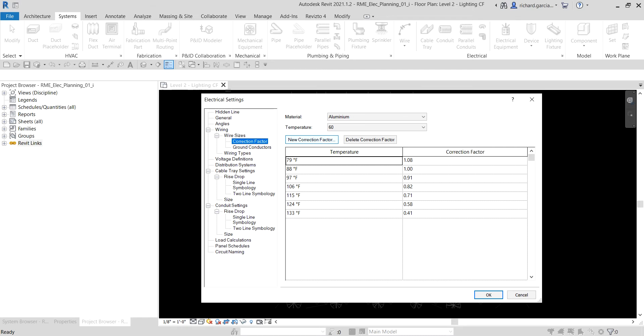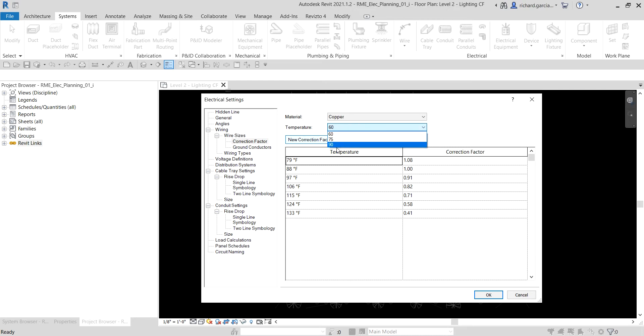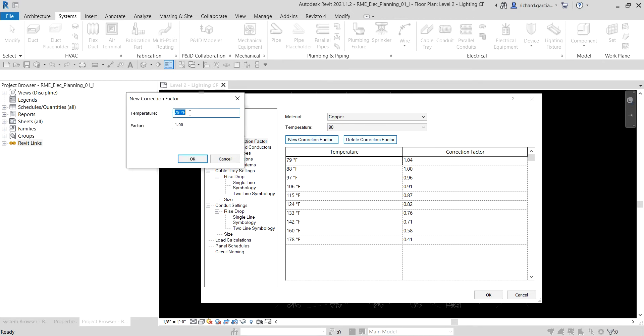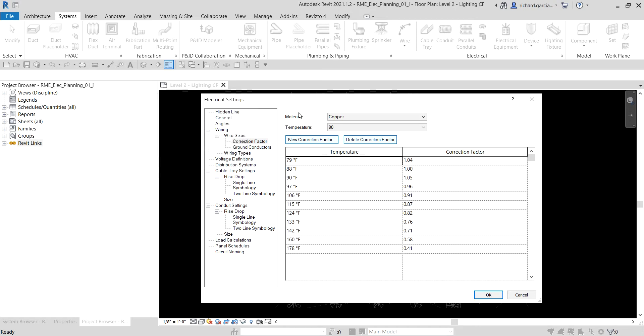You can click New Correction Factor to add custom correction factors to a project. For this example, I'll select Copper as the material from the dropdown — we have Aluminum and Copper available. I'll select a temperature of 90, then click New Correction Factor, type 90 for the temperature and 1.05 for the correction factor value, then click OK. The new correction factor is now added.